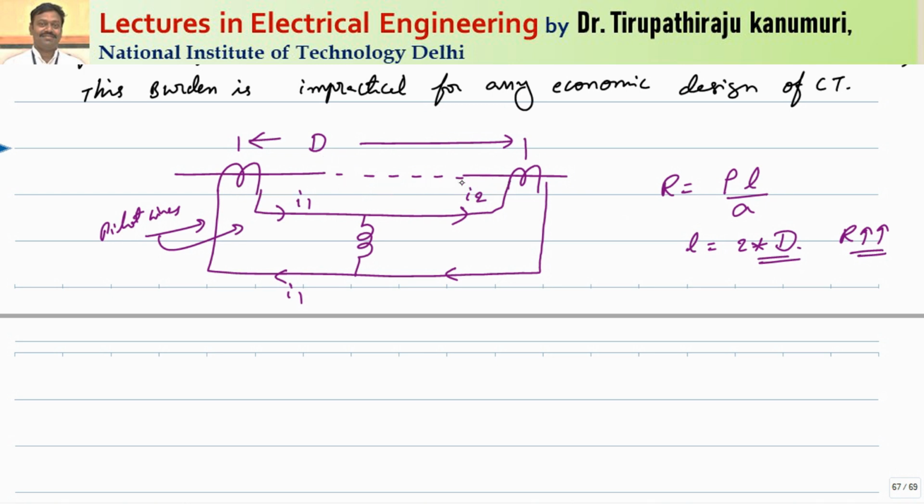But let us take the case where I want to protect a feeder. Generally a feeder will be in kilometers. When you go for such a large length in kilometers, the resistance increases drastically. So there will be continuous I square R losses in your pilot wires, because the CT secondary is generally rated for 5 amperes, as we already discussed, so continuously 5 amperes will pass through them.